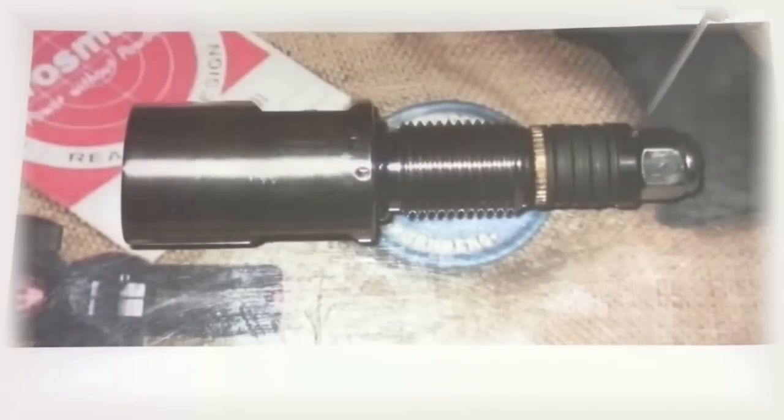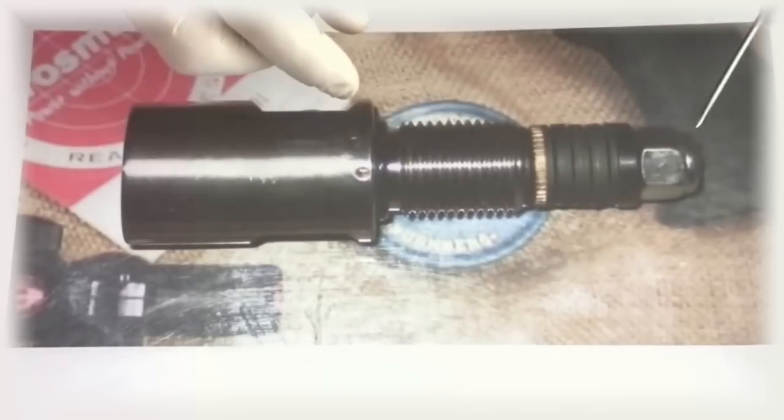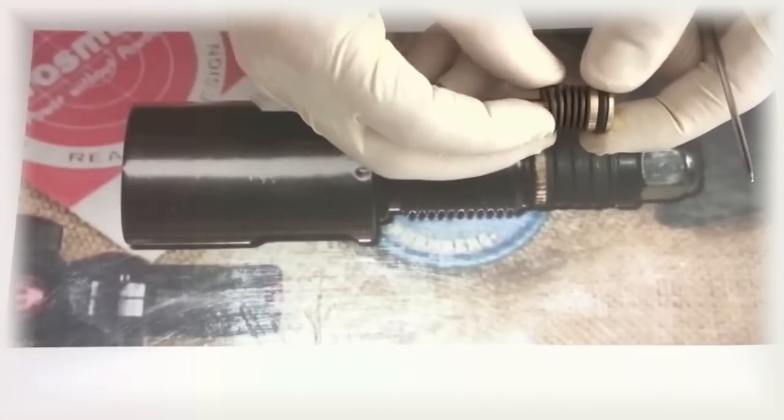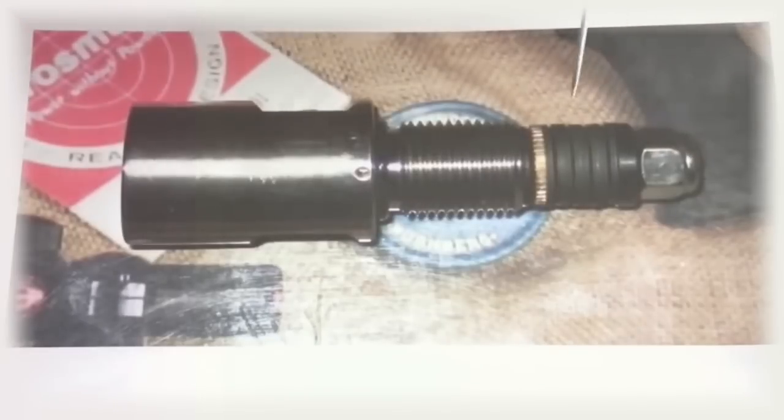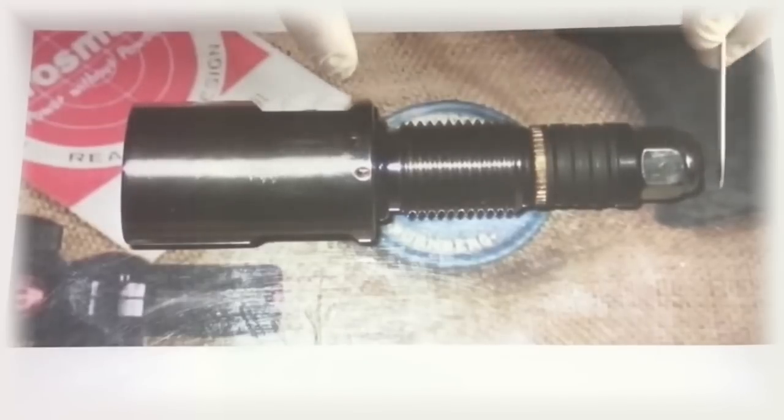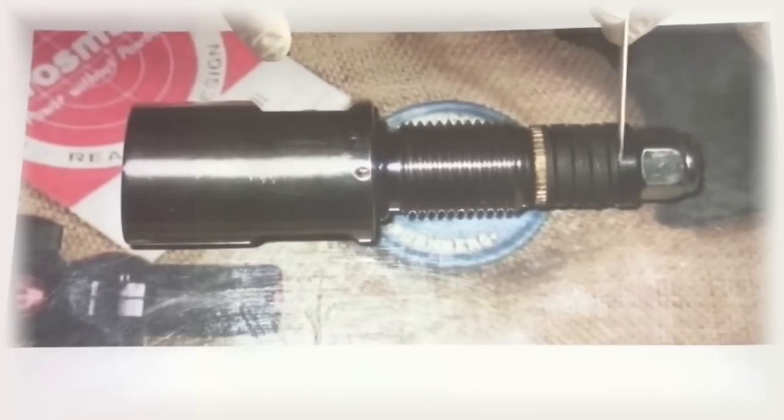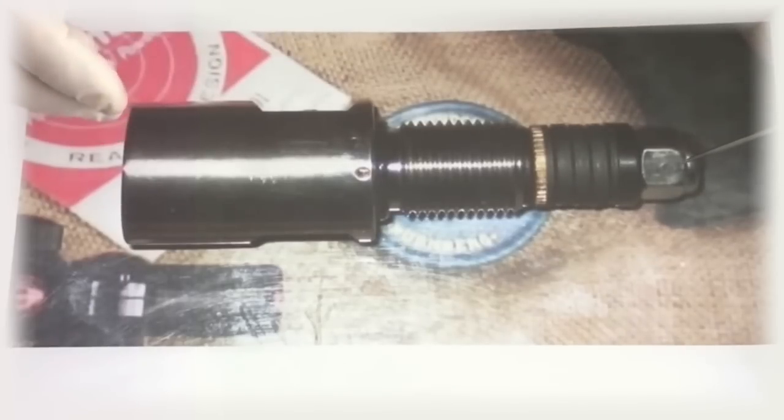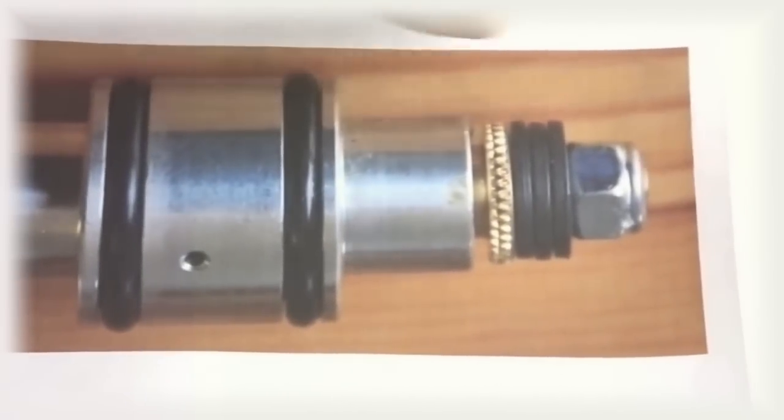Obviously on the Rapid, once you take the bottle off of this end, the chamber in here, the air has also gone in there. On the conventional design, the piston moves about when there's no pressure in there, these washers can move about. This problem is overcome by having a limited movement on the piston in here but more movement via this nut and the compression on the Belleville washers at this end. So that when the air is removed from the chamber when the bottle is taken off, these washers still stay under compressive force and aren't liable to move and give a different pressure reading when the bottle is reattached and the chamber is re-pressurized.